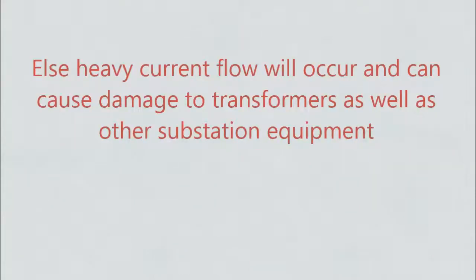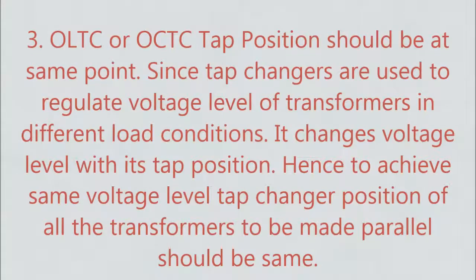Otherwise, heavy current flow will occur and can cause damage to transformers as well as other substation equipment. The third condition is that the OLTC or OCTC tap position should be at the same point. Tap changers are used to regulate the voltage level of transformers in different load conditions — they change the voltage level with their tap position. Hence, to achieve the same voltage level, the tap changer position of all transformers to be paralleled should be the same.